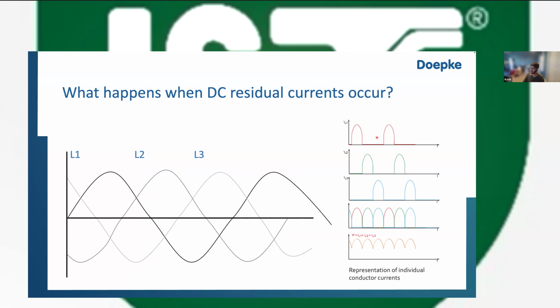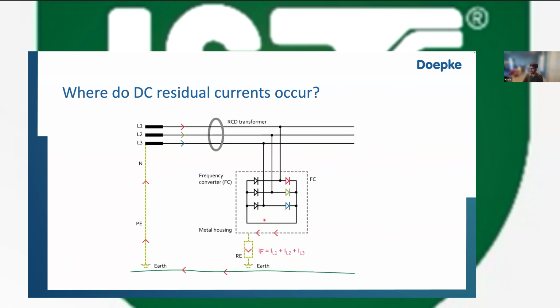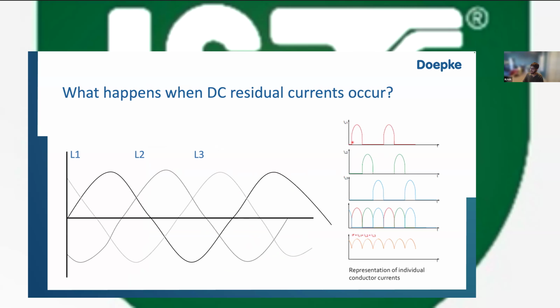And what happens when DC residual current occurs? So if we talk about this specific example again, in the first cycle, you get a peak, then for 2 cycles, nothing, then another half cycle run. Once again, third. And what is the combination? IF, it looks like this. So it looks like you're getting these peaks superimposed upon a certain level of smooth DC.